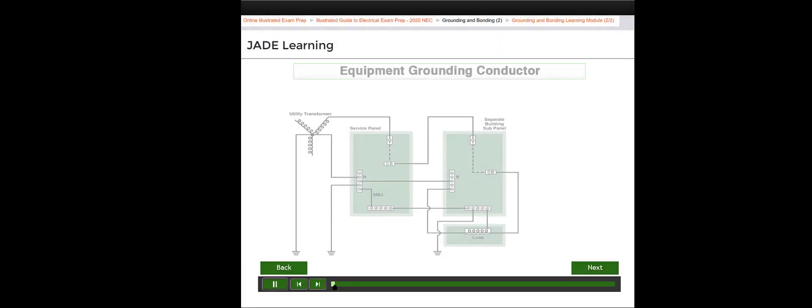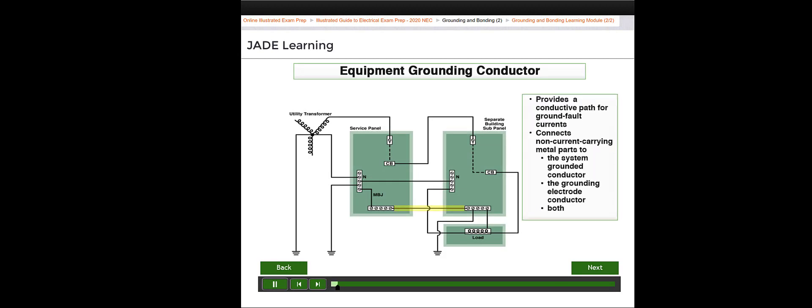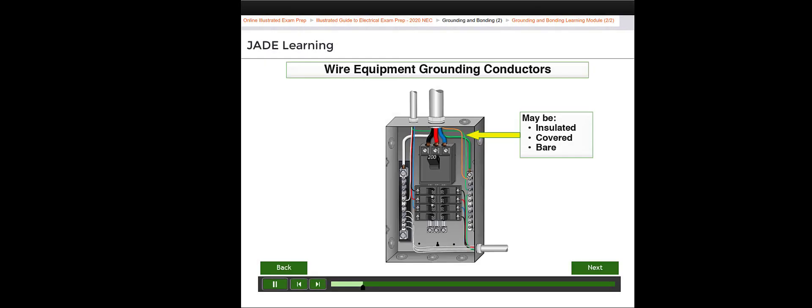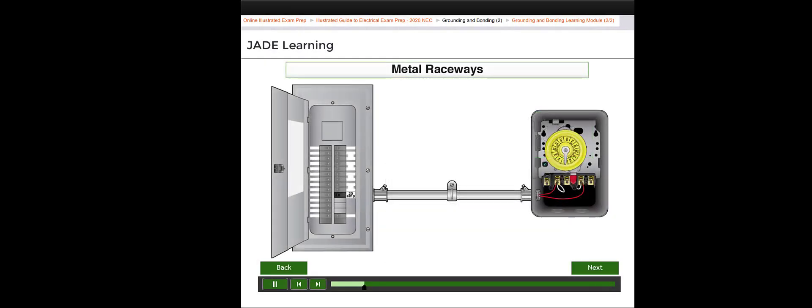An equipment grounding conductor provides a conductive path for ground fault currents from the normally non-current carrying metal parts of equipment back to the system grounded conductor. Metal raceways such as rigid metal conduit RMC, intermediate metal conduit IMC, and EMT are also equipment grounding conductors.